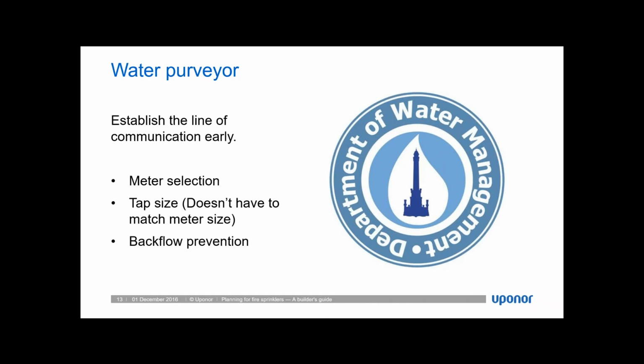Now, I've talked quite a bit about water purveyors, and I just want to make sure to stress the importance of establishing a line of communication with your local water purveyor. They're going to be the ones to decide what kind of meter is installed. Again, the tap size, which does not have to match your meter size. They're going to be the ones enforcing any requirements for backflow prevention. And they're going to be the ones to usually allow for larger than normal supply line sizes.